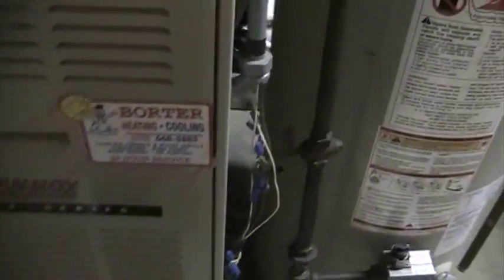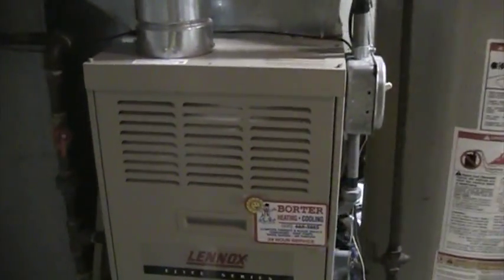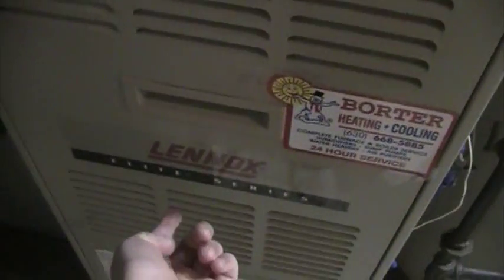But this particular furnace, when it turns off, first the burners will go off, five seconds later the draft inducer comes off, the blower runs for five minutes, shuts off, there you go.